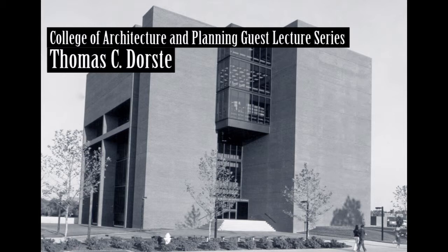We also looked at, here again, variable volume, which incidentally works extremely well in a large building which has a specific time of use, like 8 to 5 and 3 hours for cleaning or whatever. We looked at this and we took the next step, which said we'll heat the space above the ceiling on the top floor with unit heaters on their own thermostats to take care of the nighttime loss through the roof, so that there will be no loss from the interior space below it.